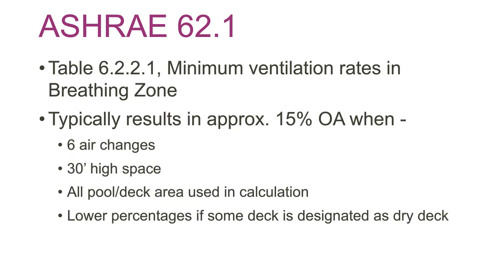So it talks about the minimum rates in the breathing zone, and it typically is going to result in about 15% outside air if you design on 6 air changes of air movement, which is common, if you have a 30-foot high space, which is common, and you use all the pool deck area in that calculation. If you designate some as dry deck, it could get a little bit lower.